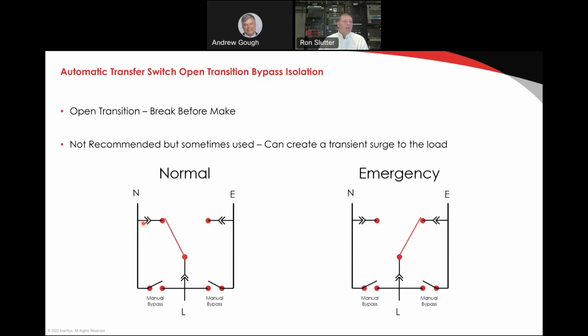Okay. What do these little arrows mean? These little arrows, they don't mean the direction of current flow. They mean that the piece of equipment on the inside of the arrows is considered draw out. That means with power active on these circuits, we can still remove the interior portion of the ATS and work on it and then put it back in after we've maintained it. So this makes it very easy to deal with an ATS and the maintenance that's required for an ATS.